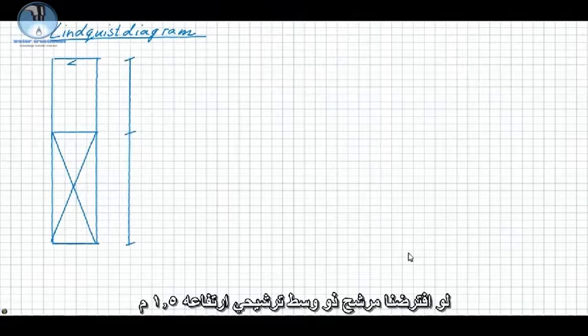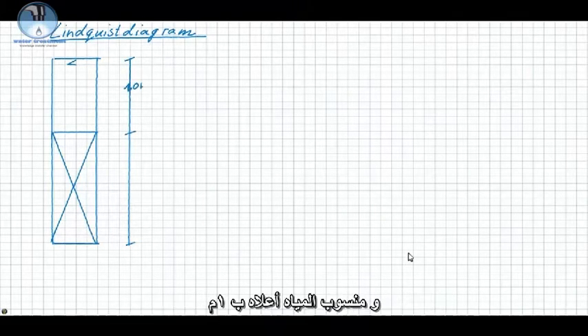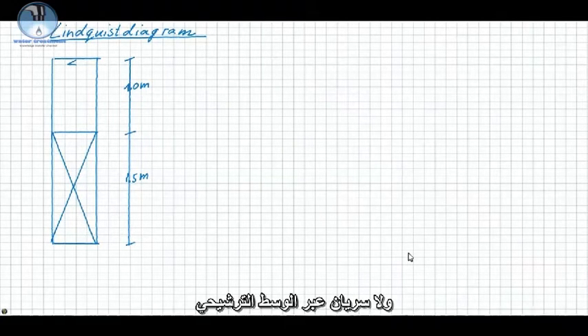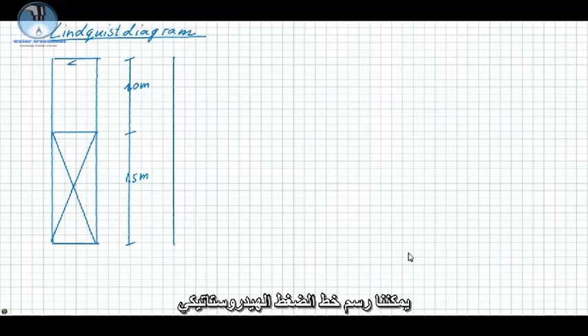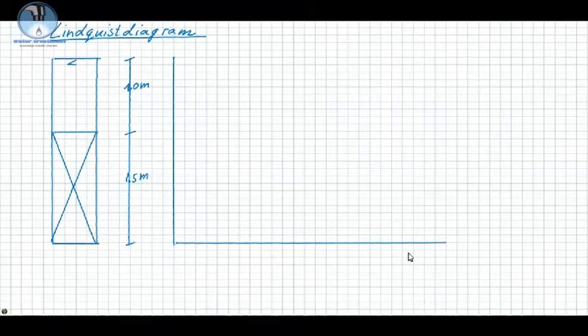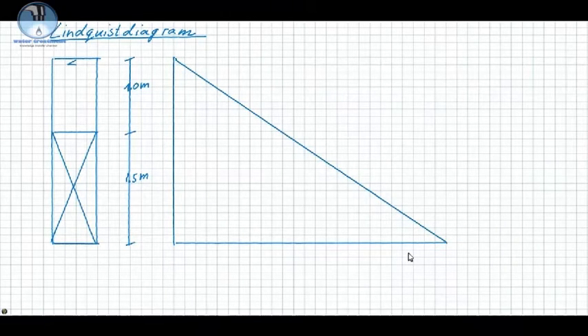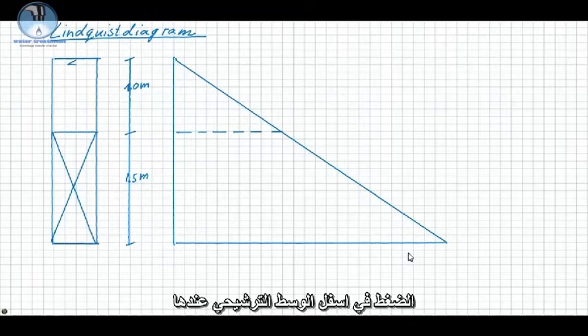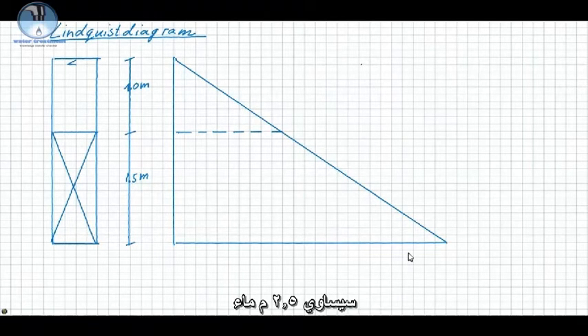When we consider a filter with a filter bed height of 1.5 meter and a supernatant water level of 1 meter above the filter bed, and there is no flow through the filter, then we can draw the hydrostatic pressure line. The pressure at the bottom of the filter bed is then 2.5 meter water column.